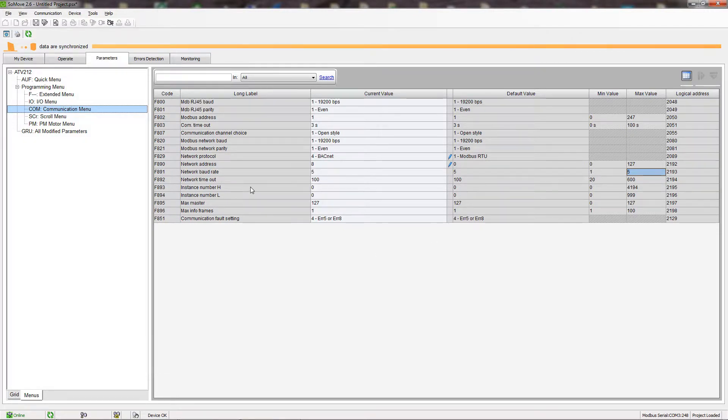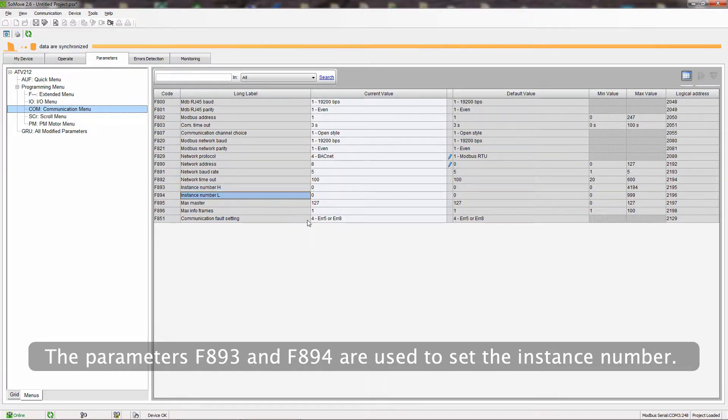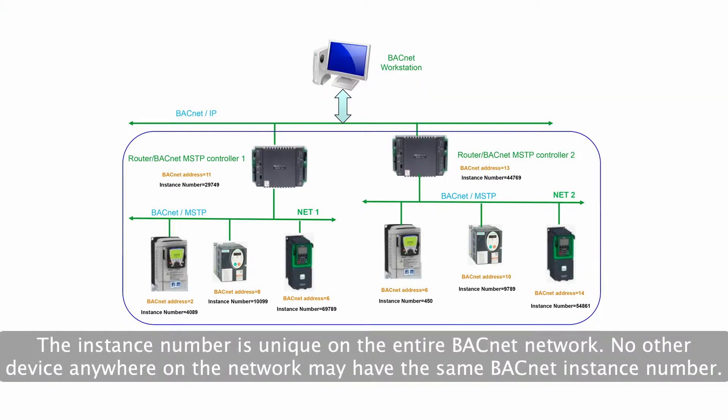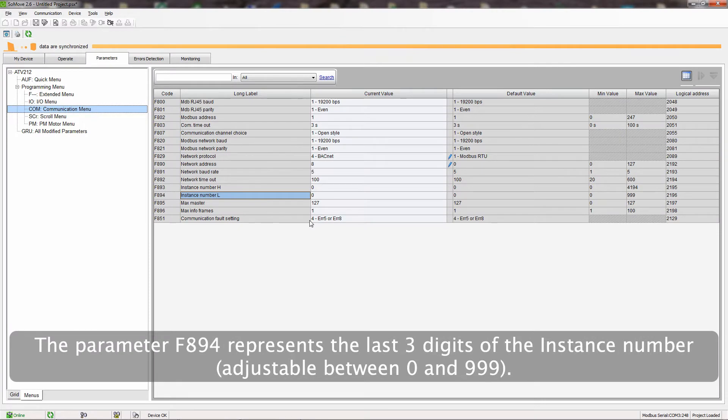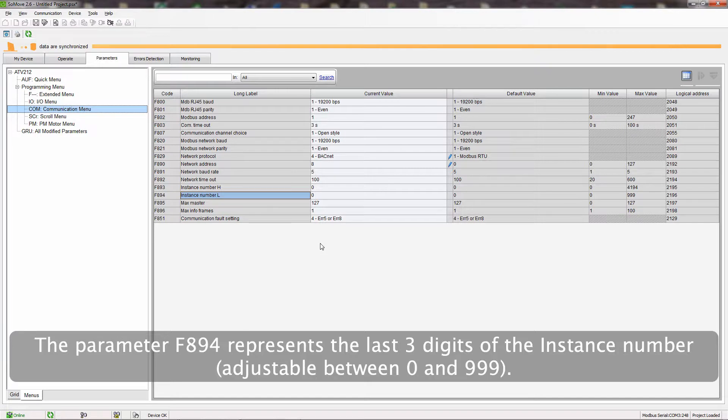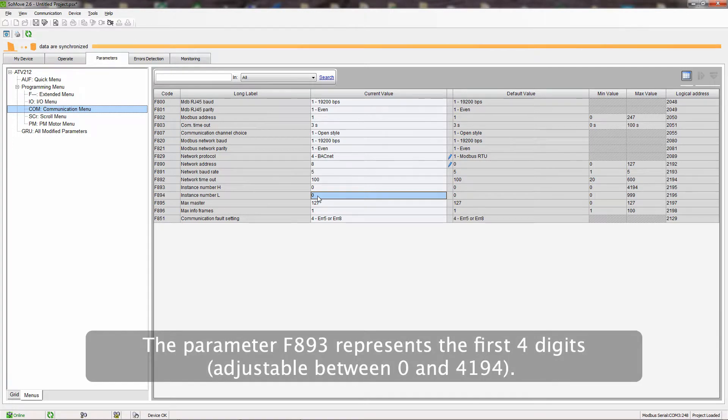The parameters F893 and F894 are used to set the instance number. The instance number is unique on the entire BACnet network. No other device anywhere on the network may have the same BACnet instance number. The parameter F894 represents the last three digits of the instance number. The parameter F893 represents the first four digits.